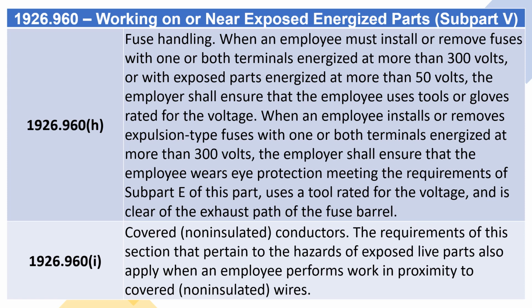1926.960 H. Fuse handling. When an employee must install or remove fuses with one or both terminals energized at more than 300 volts, or with exposed parts energized at more than 50 volts, the employer shall ensure that the employee uses tools or gloves rated for the voltage. When an employee installs or removes expulsion-type fuses with one or both terminals energized at more than 300 volts, the employer shall ensure that the employee wears eye protection meeting the requirements of Subpart E of this part, uses a tool rated for the voltage, and is clear of the exhaust path of the fuse barrel.